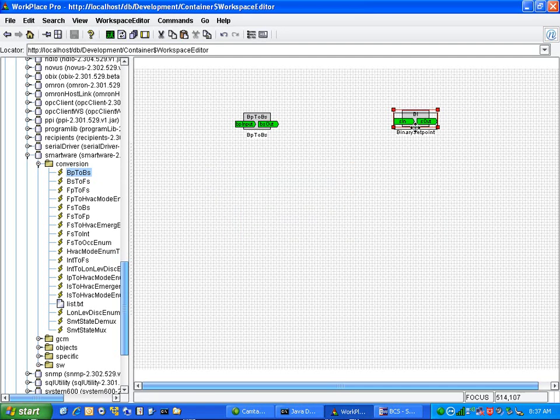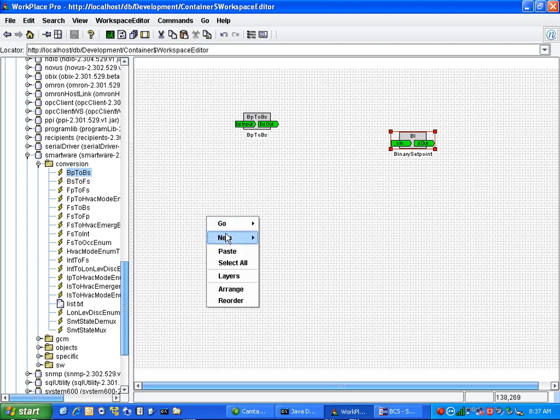This would represent a value we're sending down to. Let's pretend this is the schedule. In the schedule, we didn't want any right-click functionalities on this block or anything. We just wanted a straight single shot, and you'll see on its input side of the object, its input is an SIN, which stands for a status input. There's a difference between a priority input and a status input.